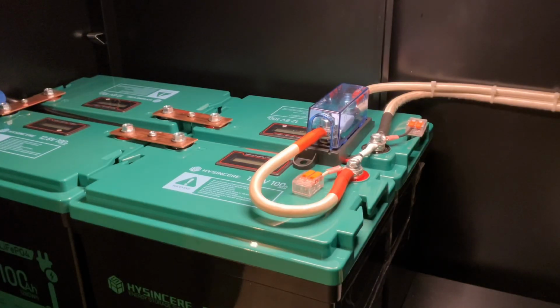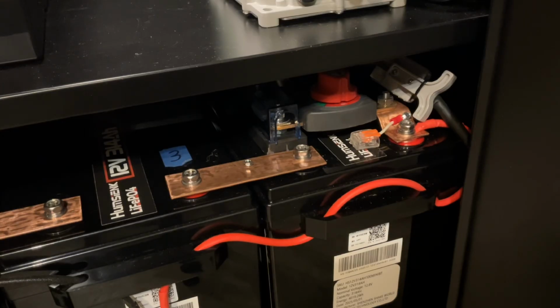I'm going to begin disconnecting the wires to this battery bank and removing the bus bars so I can reconfigure the battery bank and eliminate this potential shock or short circuit hazard. I've already turned off the battery disconnect switch for the Humsienk batteries, so the Hysincere and Humsienk batteries are no longer in parallel.